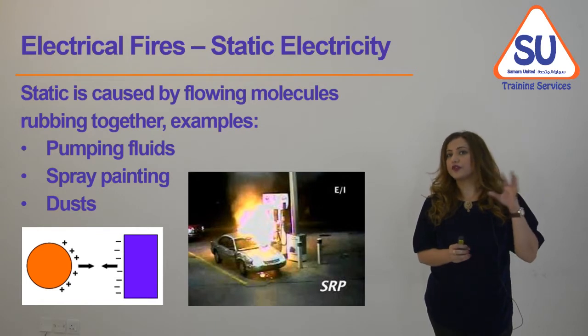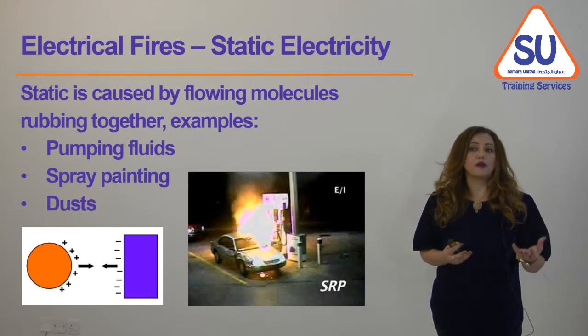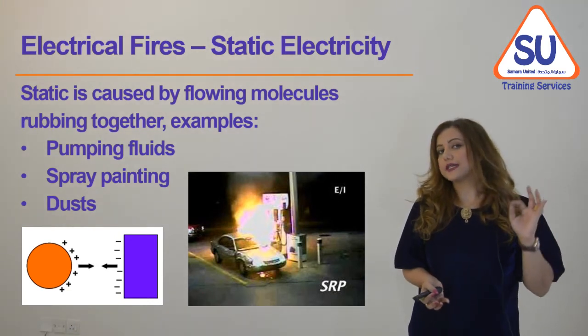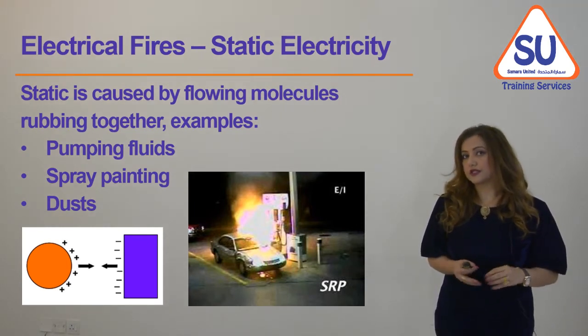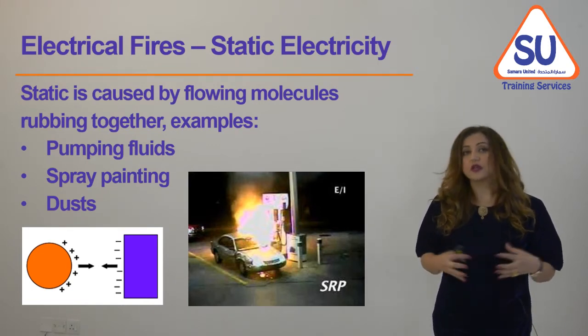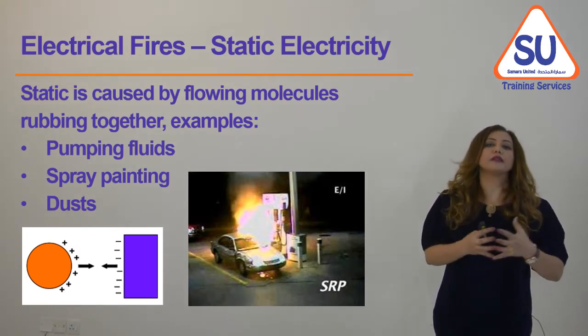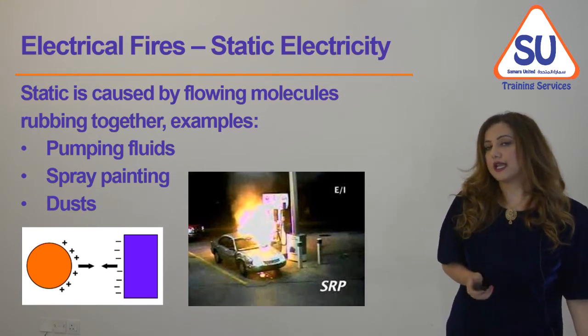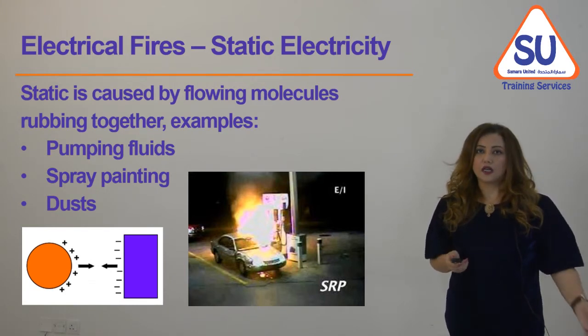When we talk about electrical fires, we should not forget static electricity, which can be associated with pumping of fluids, spray painting, and dust in the workplace. It is a real challenge, particularly in explosive atmospheres. Many people tend to forget about static electricity. In such cases, we must provide workers with special antistatic safety boots and special overalls made of specific materials, and limit the movements of people and equipment to a very controlled level. The spark associated with static electricity could easily start a fire.